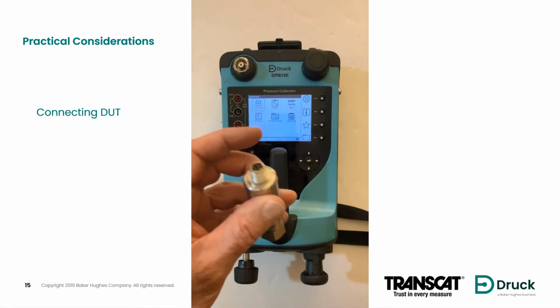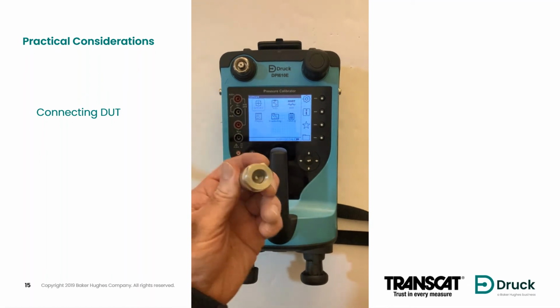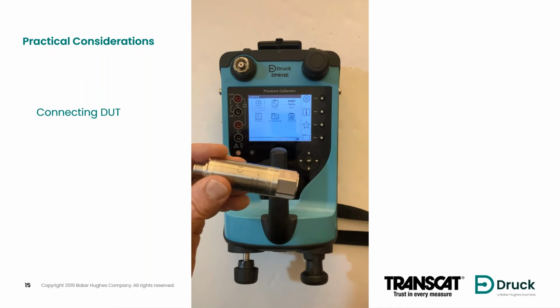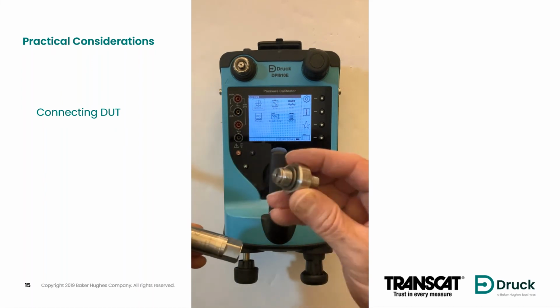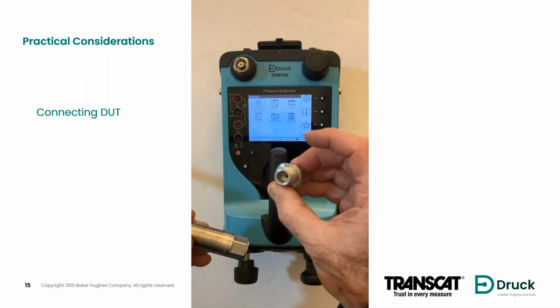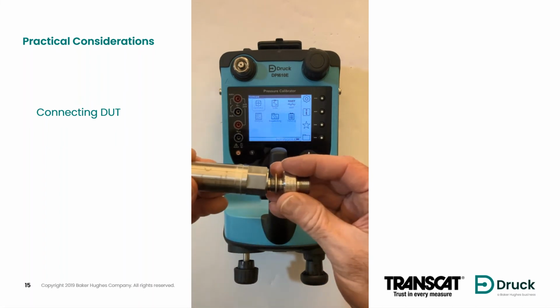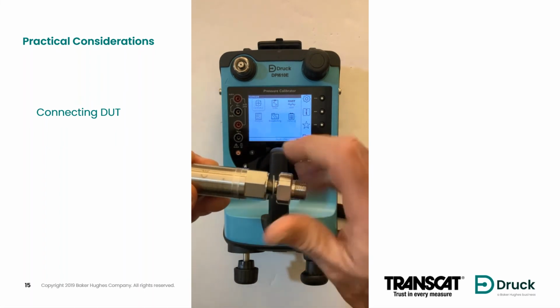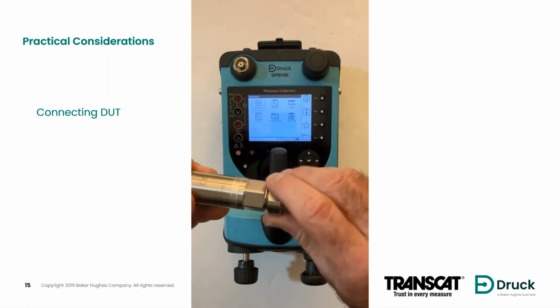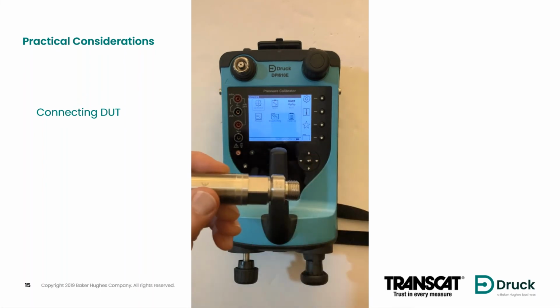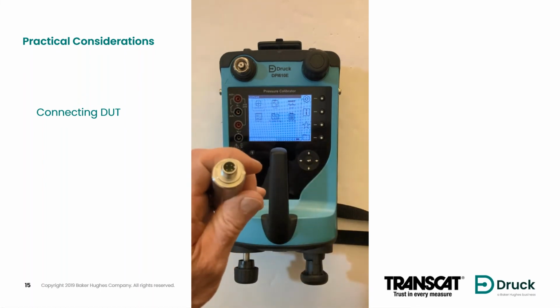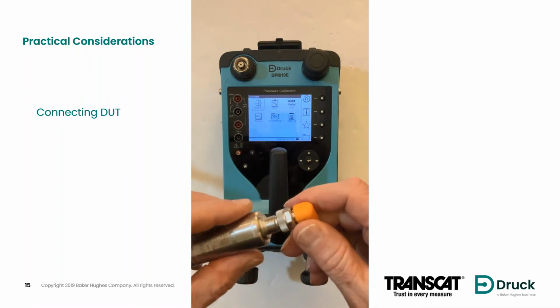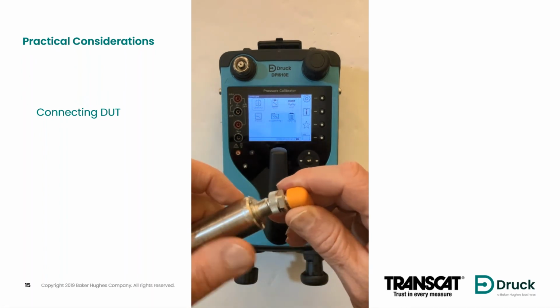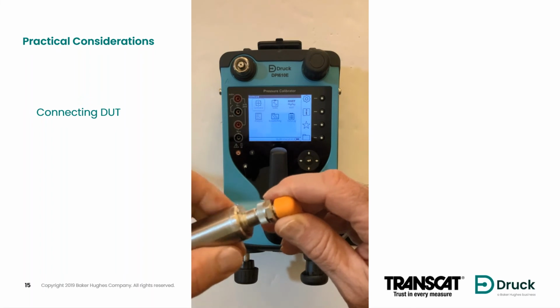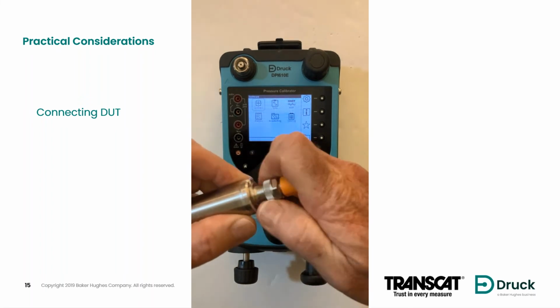So here I'm showing you just a standard spark plug type pressure transmitter. This is one of ours. It's a UNIK 5000, and there's an adapter that's going to enable us to connect the transmitter, which is our device under test, to the portable calibrator. And then I'm going to connect my test leads to the electrical connector to be able to energize it and read the output from it.